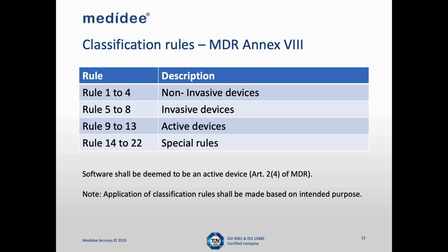And it is important to understand that software is also deemed an active device, and the application of such classification rules needs to be made based on the intended purpose. As we know, the intended purpose is what makes a device fall within the scope of the medical devices or not. So it is also important that the classification of any particular device which is to be governed by the medical device regulations is done based on its intended purpose.